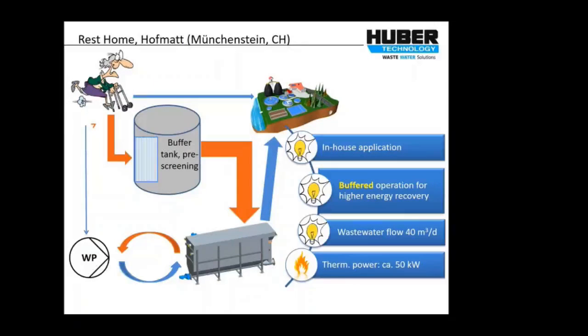So you want to buffer it, capture all the laundry water, keep it in a warm water tank, and then send it through our heat exchanger at the maximum rate the heat exchanger can cope with. In this instance it was 40 cubic meters a day, and the thermal power generated was 50 kilowatts.